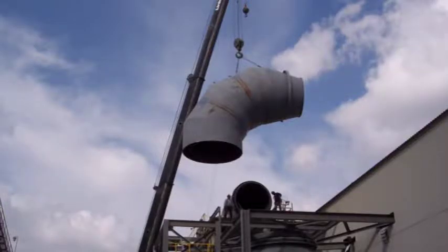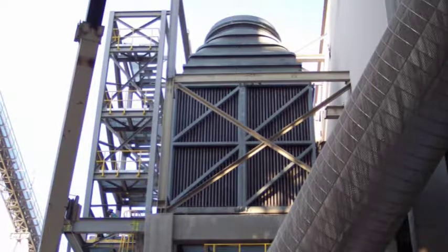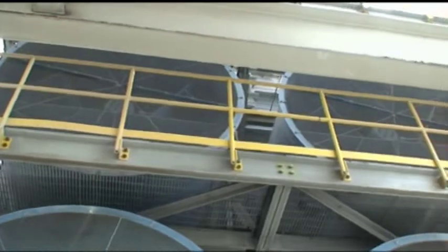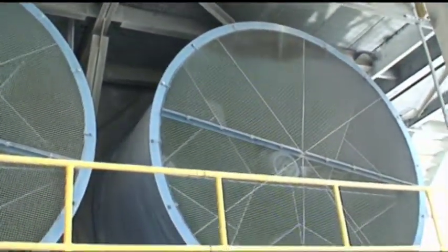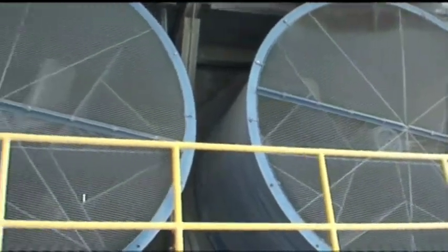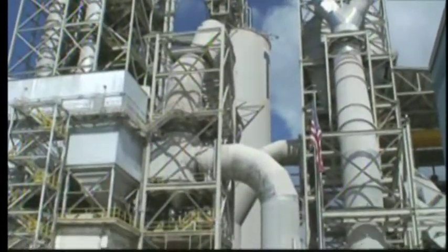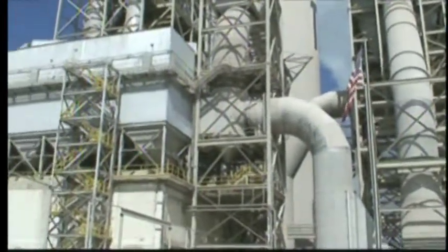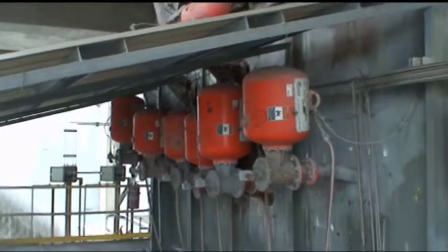The addition of the heat exchangers in the ductwork leading to the vent fan cooled the air temperature by as much as 500 degrees Fahrenheit before reaching the fan. The previous problems of the vent fan going down on high temperature were solved. This also solved the problem of heat rushing to the dust collector inlet, adding additional protection to the dust collector and eliminating the baghouse fan from going down. This alone saves valuable time in restarting the system after an unexpected shutdown.